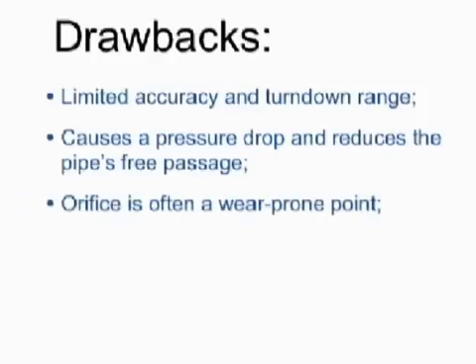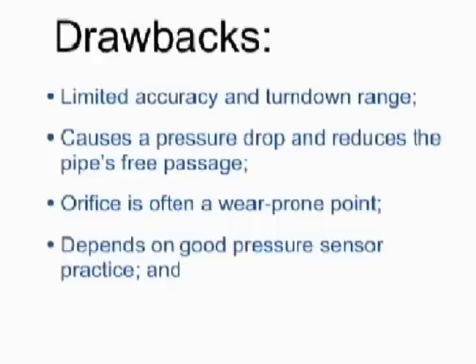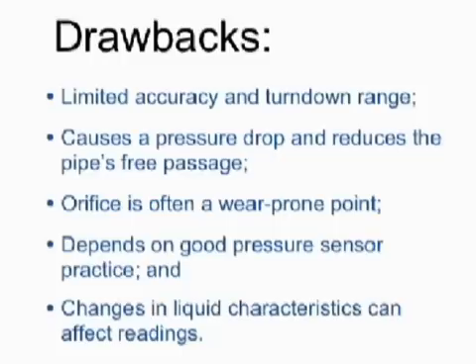The orifice is prone to wear. While there are no moving parts, the orifice itself is often a wear-prone point due to the high liquid velocity. If the orifice gradually enlarges with wear, the flow measurement will read low. On the other hand, if it becomes partly obstructed with debris, the measurement will read higher. The same application and installation guidelines for good pressure sensor practice apply here — anything that interferes with the pressure readings, such as clogged impulse lines, will interfere with the true flow calculation. Changes in liquid characteristics, including viscosity, multi-phase flow, and even temperature can affect readings. Of course, these are generalities, so discuss your specific application needs with any prospective suppliers.